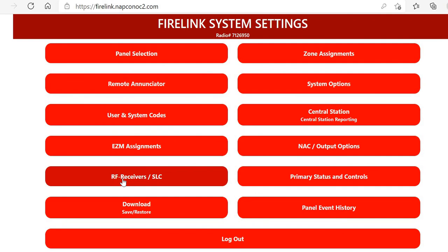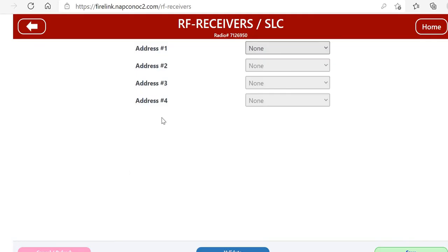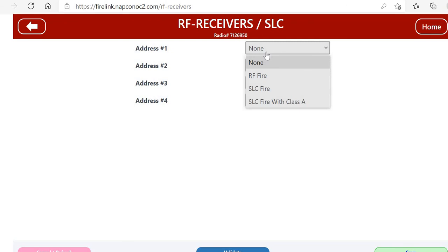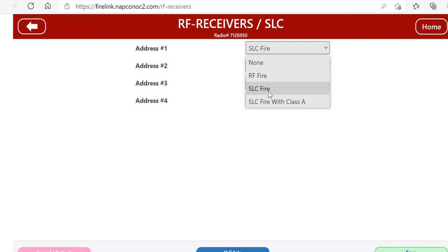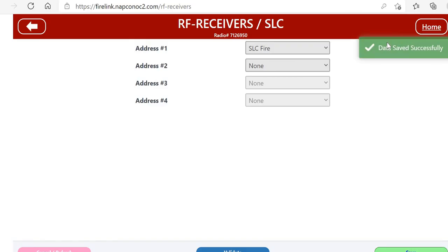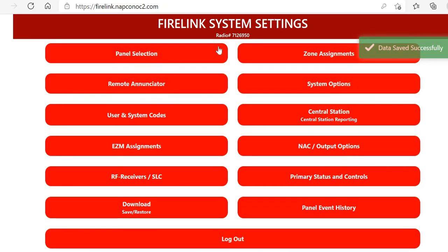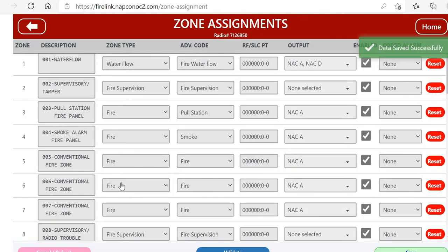If you're going to be using SLC expansion, we're going to start by going to the RF Receiver/SLC menu. We're going to add in for address one SLC Fire. It can also be done Class A if you need it. Then we would go back to our Zone Assignment section.